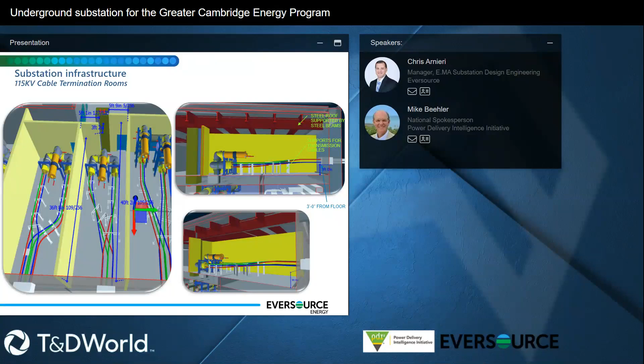So within the first 35 feet or so, passing the slurry wall of the station, we had to transition to gas insulated bus. This picture shows the different sections, the cross-linked polyethylene interfacing with the gas insulated bus. The yellow walls are blast-proof and removable.